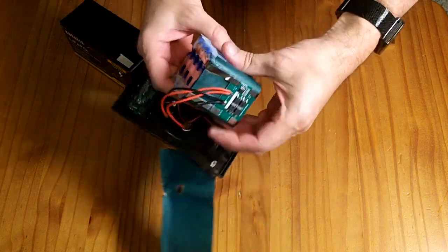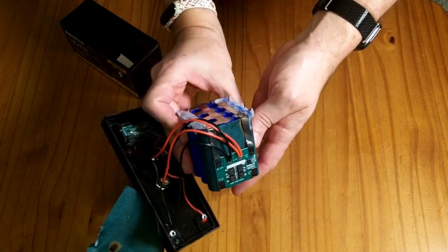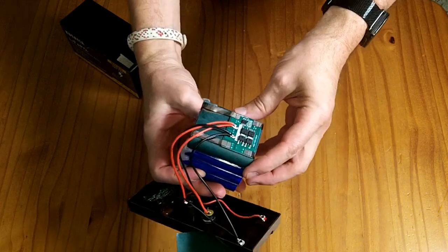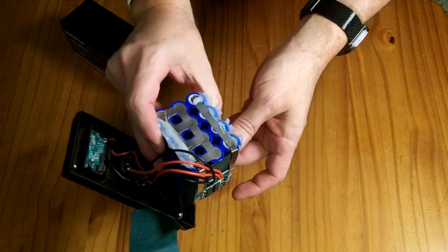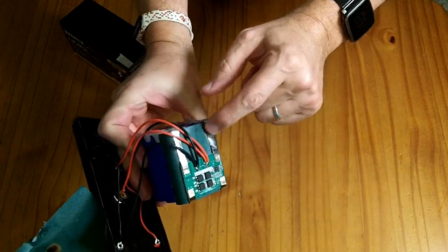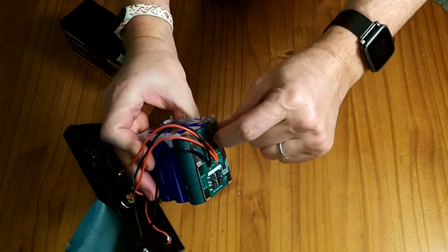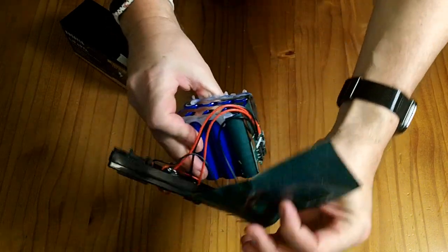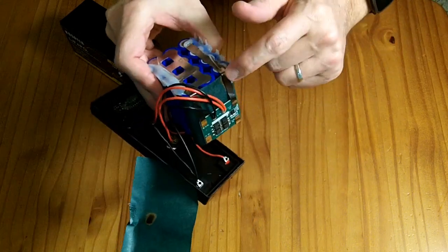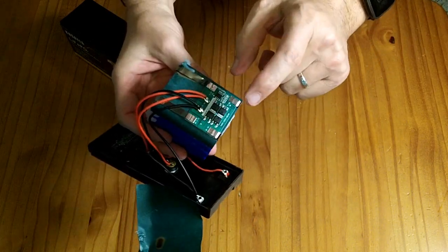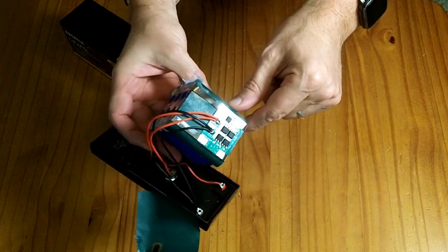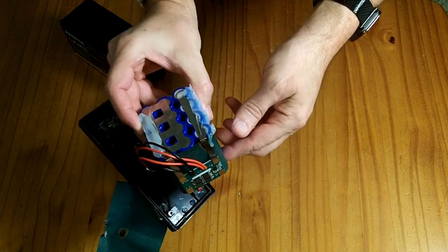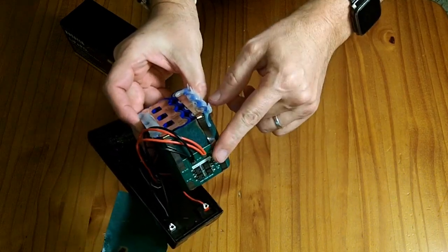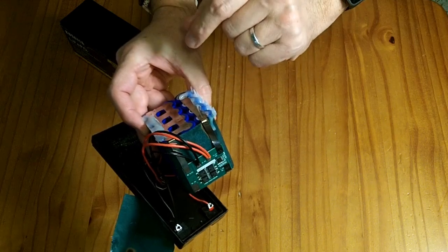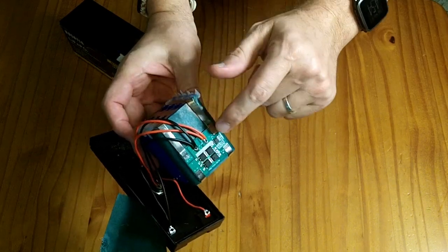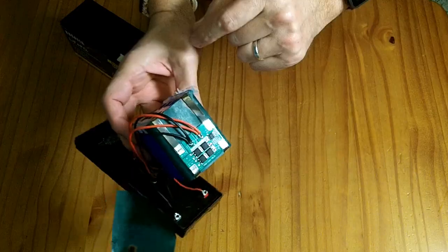The maximum current I tried to draw out of this guy was 30 amps, and the manual says you can do 30 amps for 5 seconds. But there was clearly a thermal event on this little conductor here. You can see the brown discoloration below it, and then the brown from this paper on top of it. The BMS did not shut down power for that, so I'm not sure if this BMS is correctly sized for the battery pack, or at least for this nickel bus bar here.